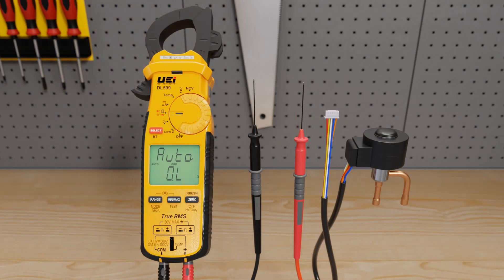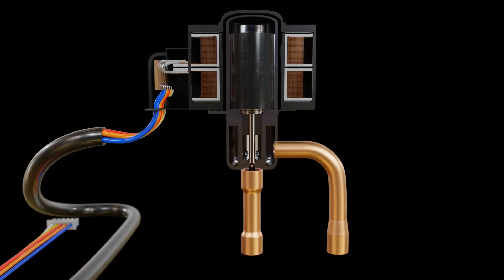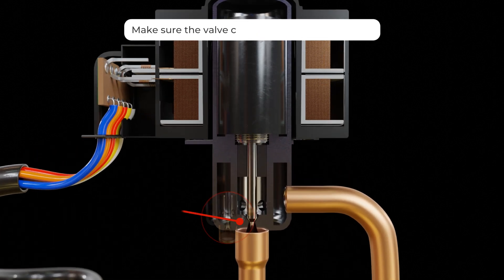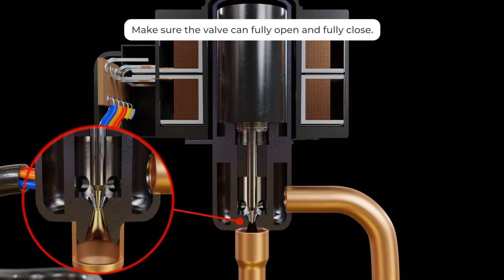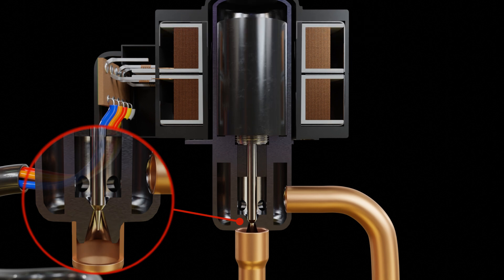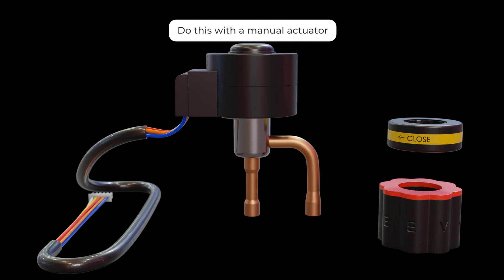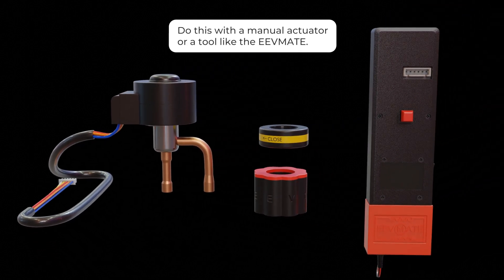When you've ruled out electrical problems, you can see if the valve is stuck from a mechanical issue. The way to do this is to make sure the valve can fully open and fully close. You can do this using a hand-powered cylindrical tool with magnets called a manual actuator or tool like the EEV Mate.